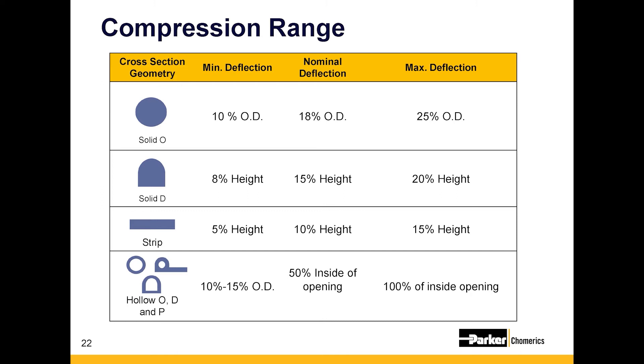The deflection ranges don't change based on the size of the gasket. For example, whether you have a solid-O profile that's 70 thousandths or a solid-O profile that's a quarter of an inch, you're still looking for that same compression percentage range.